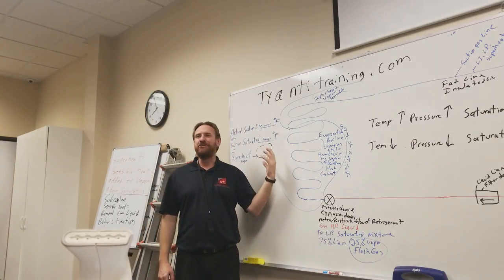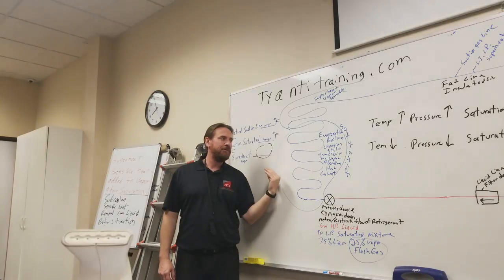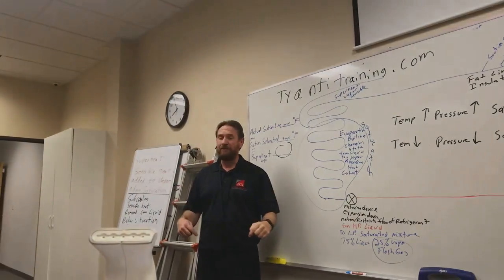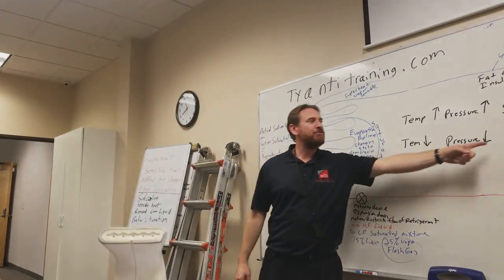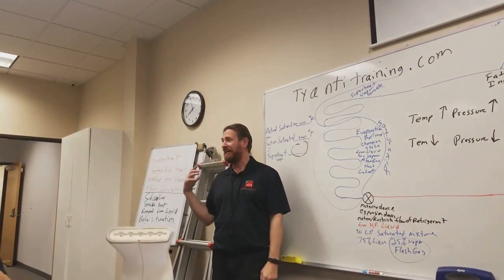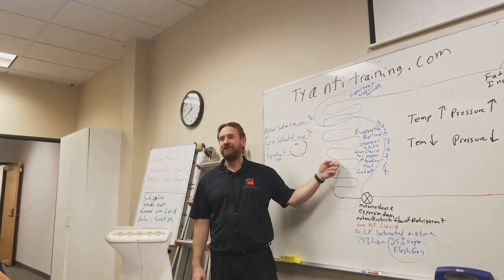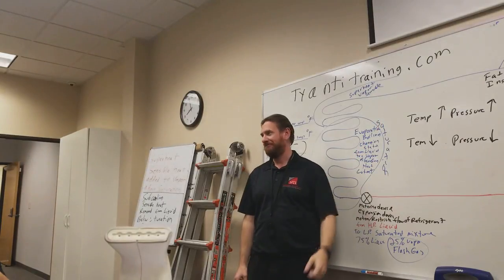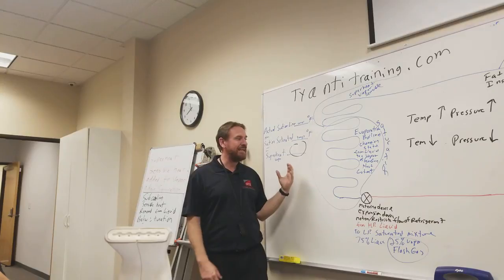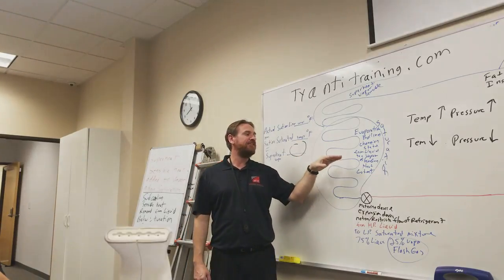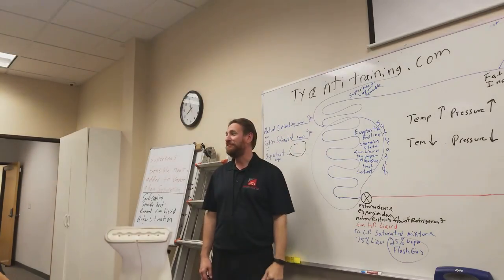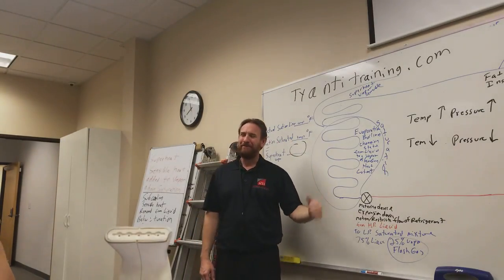So as the temperature of the air starts to drop, what is happening to the pressure of this evaporator coil? It will also drop. What will happen to my saturation temperature? It will also drop. Right? So the temperature of the air inside the house will have an effect on the suction pressure, and so will the outdoor temperature. Now, as the temperature in the house starts to go up, there's more heat in the air, and the more heat's reacting against this, what's going to happen to my suction pressure? It's going to go up. And what's going to happen to my suction saturated temperature? It's going to go up, right?